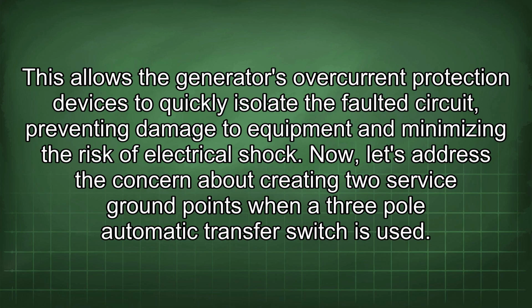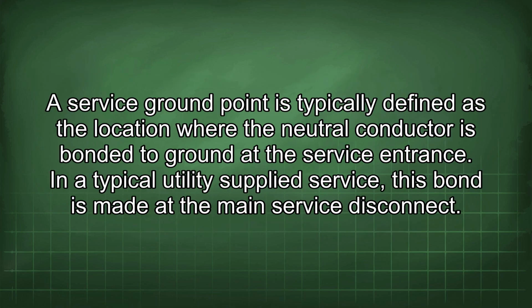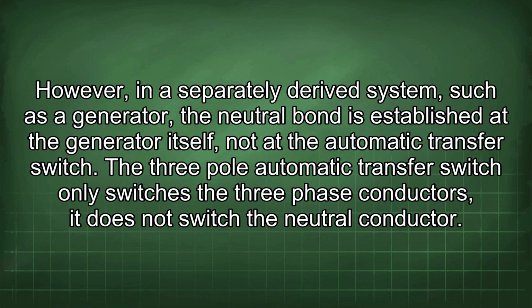Now, let's address the concern about creating two service ground points when a 3-pole automatic transfer switch is used. A service ground point is typically defined as the location where the neutral conductor is bonded to ground at the service entrance. In a typical utility-supplied service, this bond is made at the main service disconnect. However, in a separately derived system, such as a generator, the neutral bond is established at the generator itself, not at the automatic transfer switch.